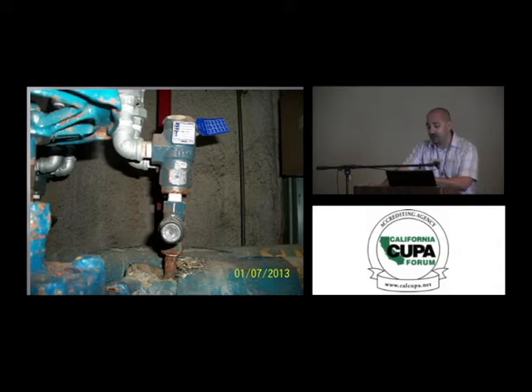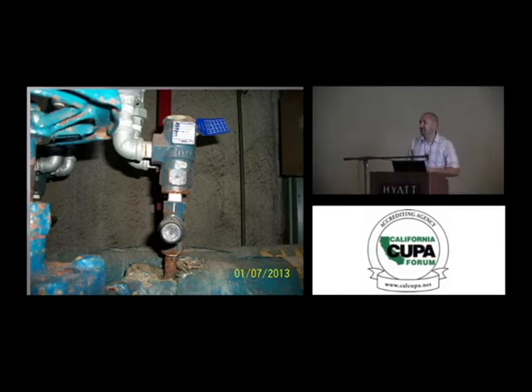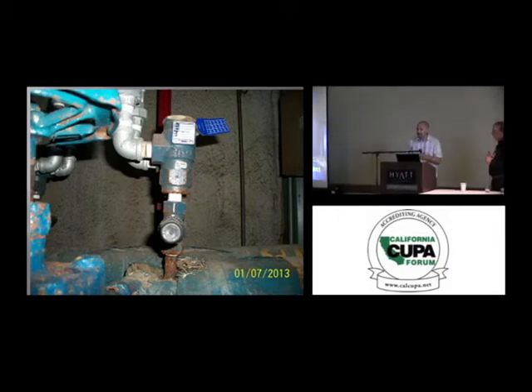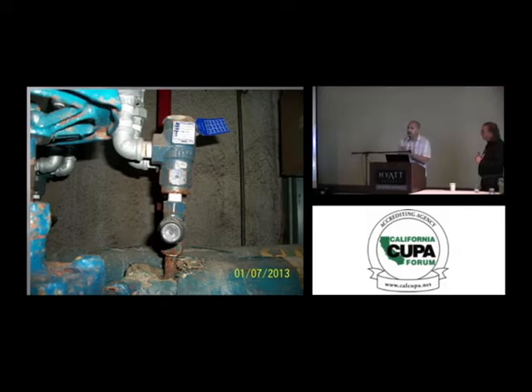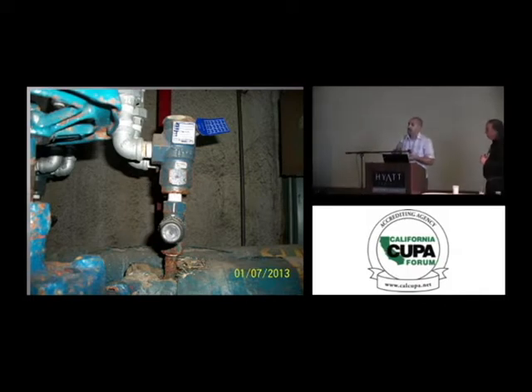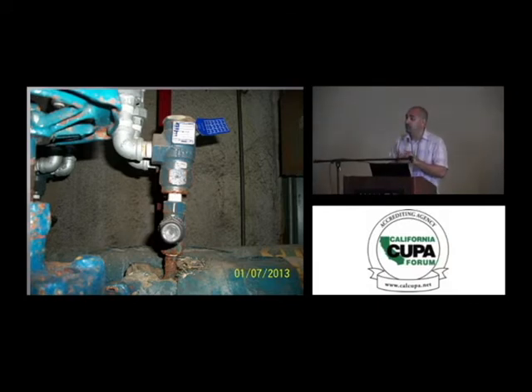And when our guy was removing the manifold for the relief valves, we were going to reuse that same three-way valve. As he put a pipe wrench to remove the pipe nipple going into the three-way valve, right at the threads, it snapped. And this system, I feel like it was a matter of days before they had a huge ammonia release. Again, a pipe nipple is one of the weakest points in the system. You remove material off of Schedule 80 pipe. This happened to be a half-inch. You remove the material off of this pipe to make the male threads. So that's a weak point.